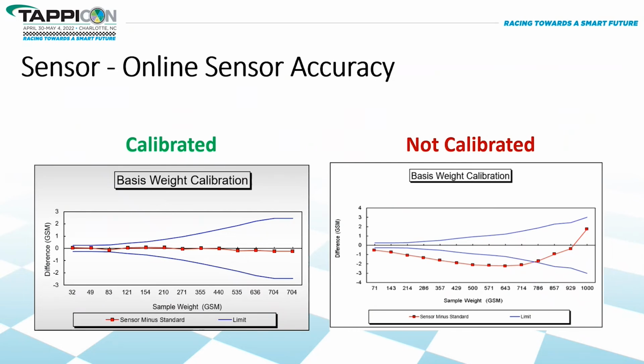First, let's take a look at this online sensor accuracy. So still many people confuse the terms sensor calibration with sensor correlation. So it's important to differentiate between the two terms. I always like to define the terms. So calibration is a comparison between a known measurement, which is a calibration standard, and the measurement using your instrument.